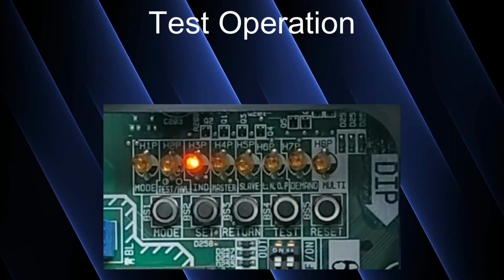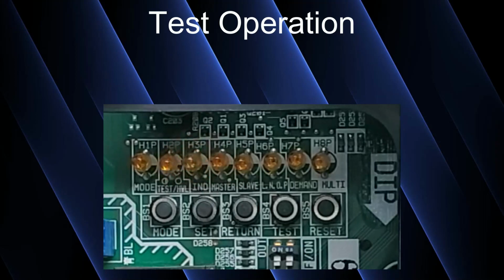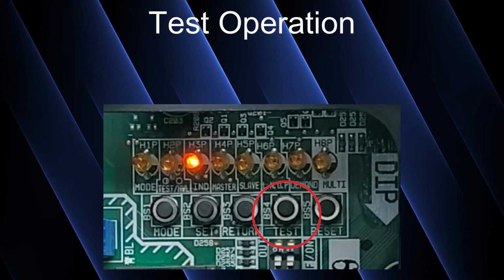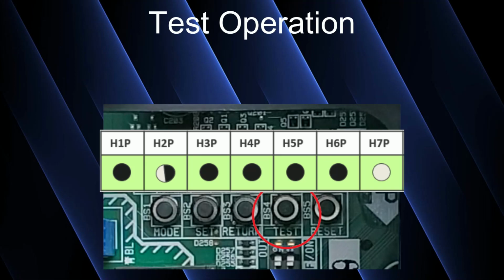When you're ready to start the test on the older PCB style with all the lights, verify that you're at the main screen. H3P is the only light on. Now simply hold the test button until 2 and 7 light up. 2 and 7 will light up. One of them will be blinking, one of them will be solid, and I can never remember which one is which for whatever silly reason, but 2 and 7 light up. Once you see that, let go.